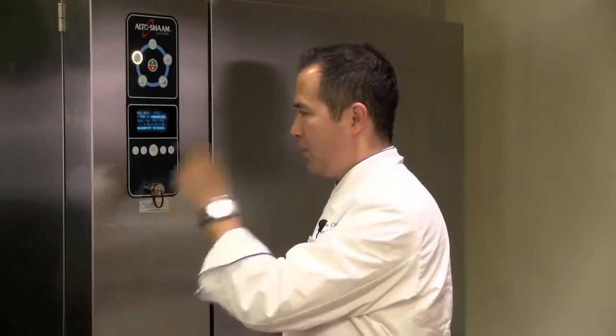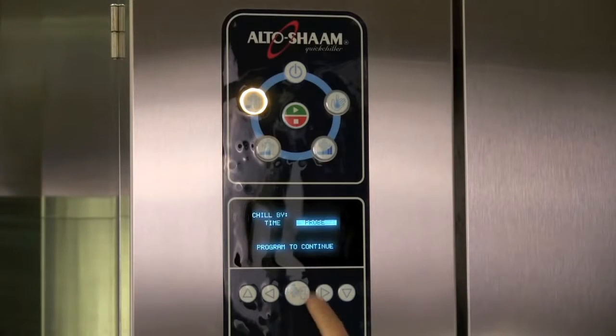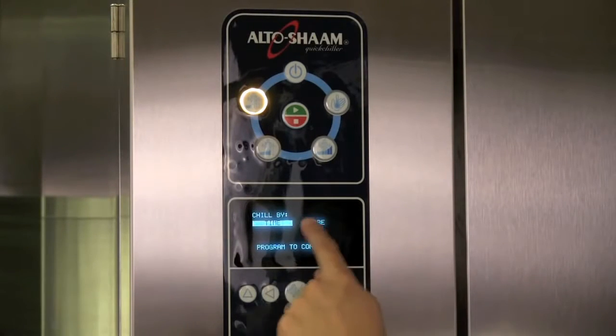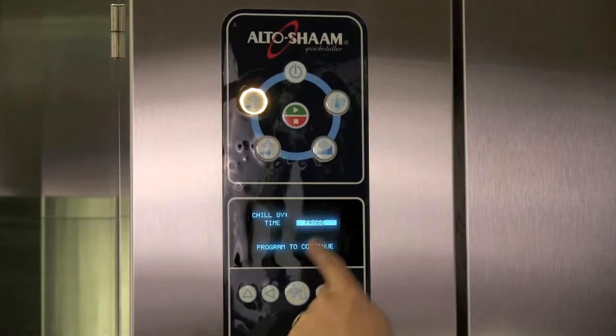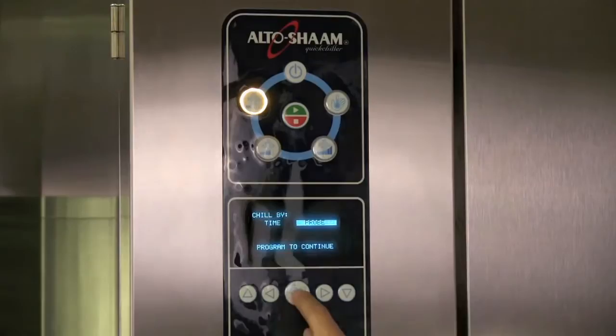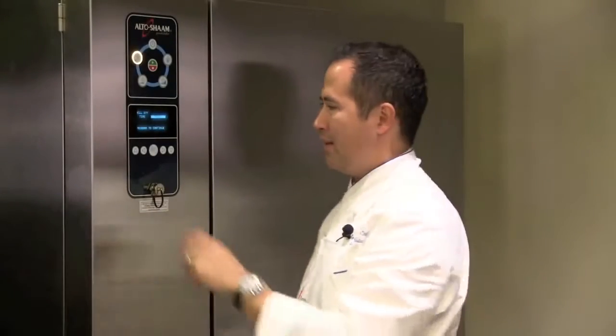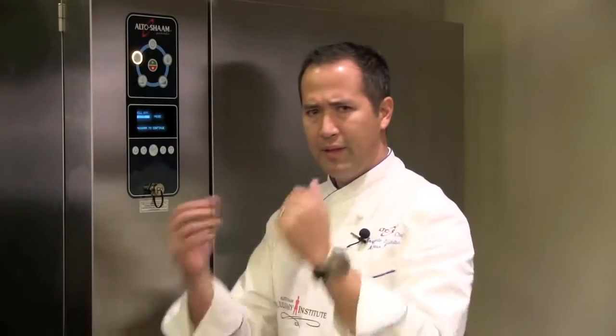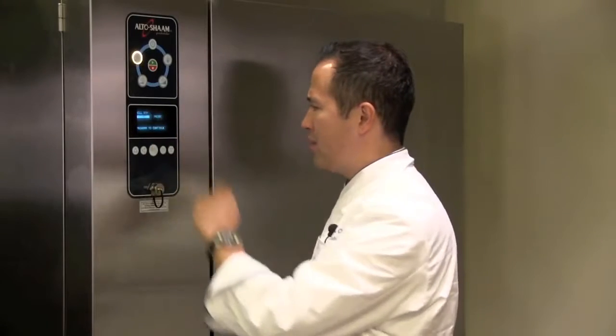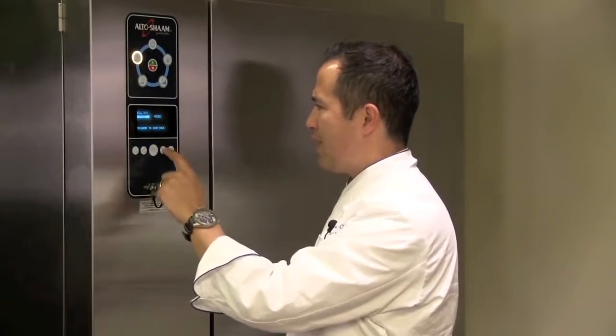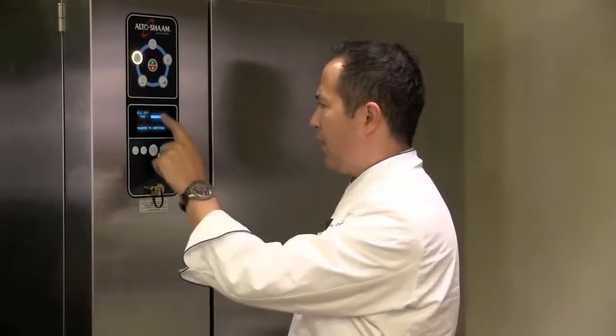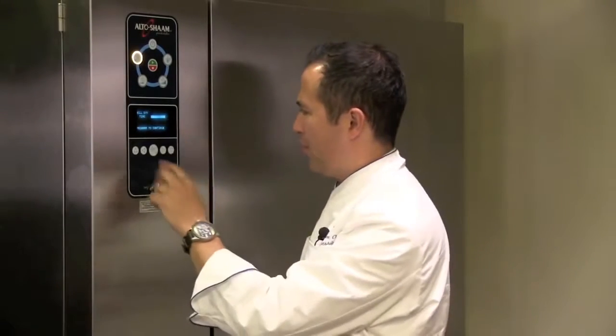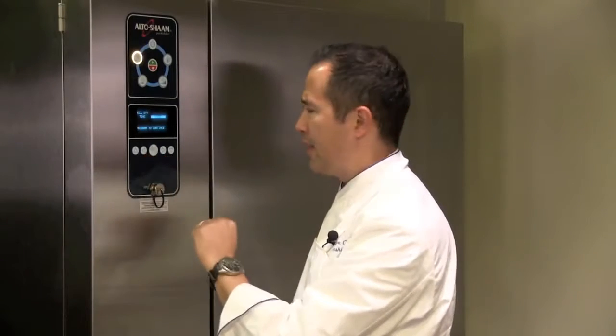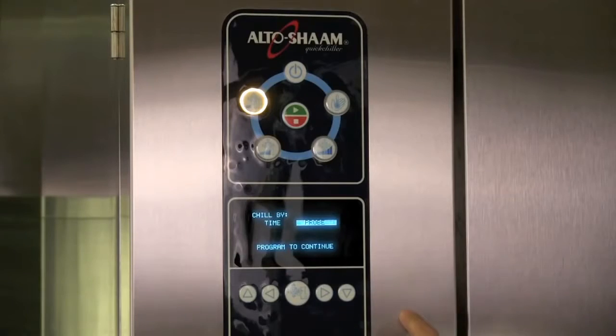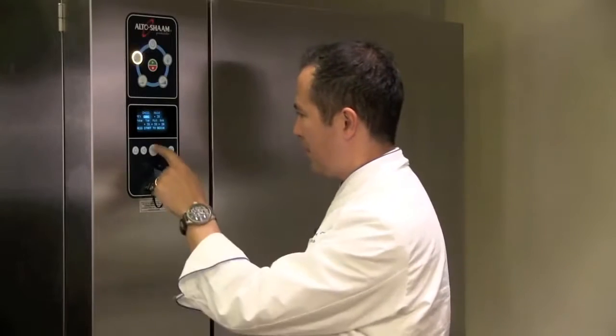How do we do that? We push this button in the center, the program button, and get a screen that says chill by time or probe—you'll see probe is highlighted. If I want to chill by time instead of using probes, I could chill for 2 hours and then let the cavity warm up to 38 degrees. I can highlight that option, but in this case I want to use the probes, so I'll leave it on probe. I go back and forth with the left and right arrows, and to continue to the next step I push the chef button and the program button.